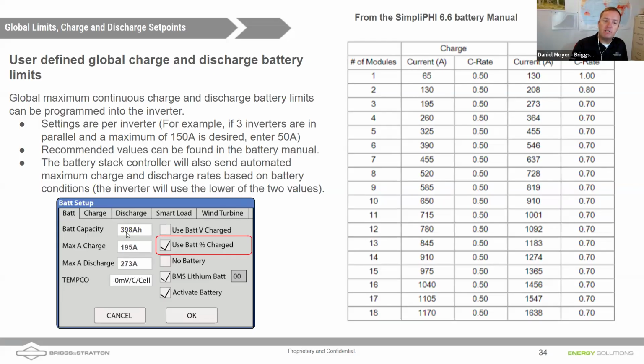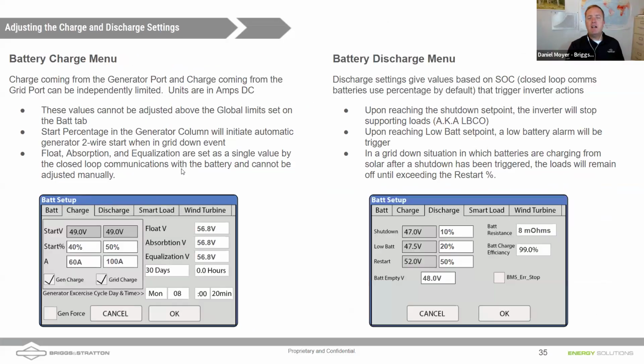This should automatically populate here through that closed loop communication, but I'd always recommend double-checking these values to make sure closed loop communication is set. That said, I don't think it'll be a big problem—if you have an 18,000 watt inverter, you're probably going to want more than just 20 kilowatt hours of storage, so most of those systems will have multiple stacks of batteries anyway.